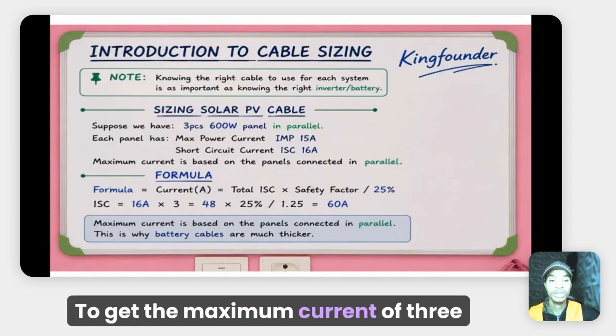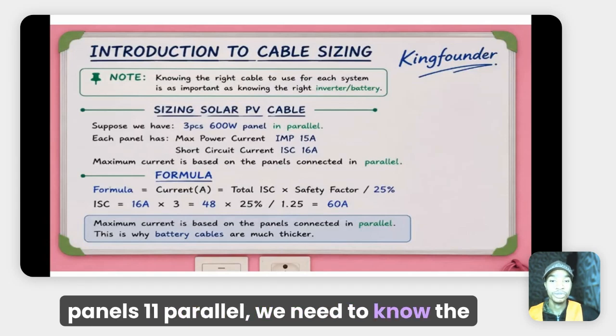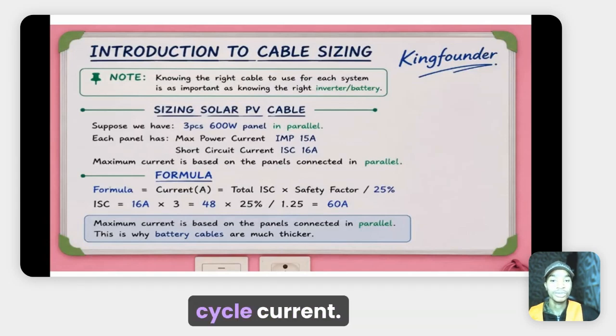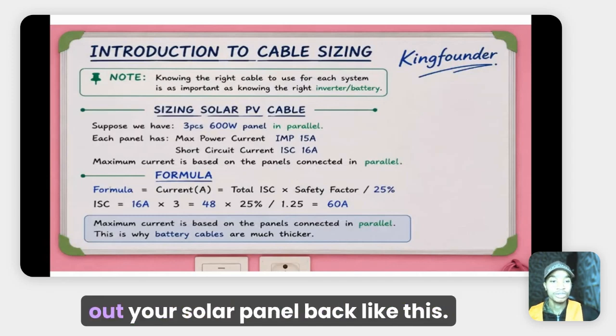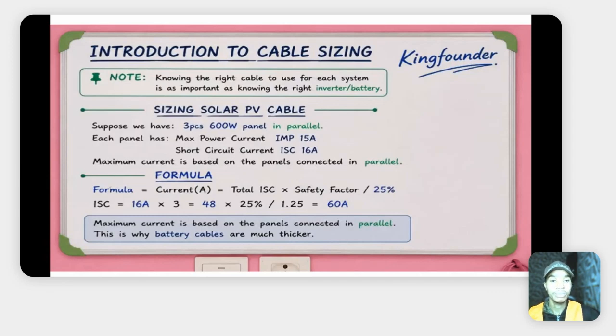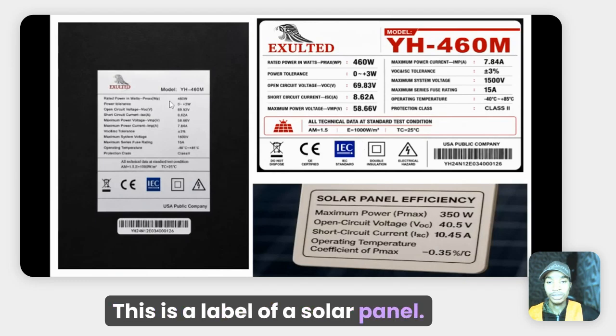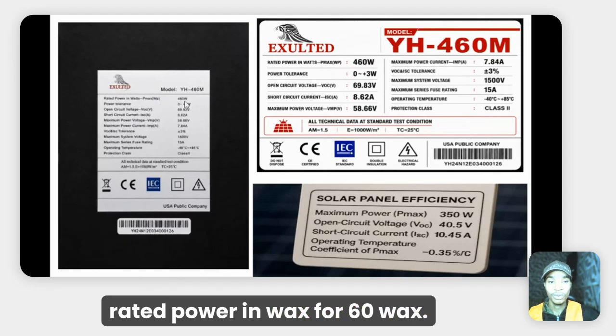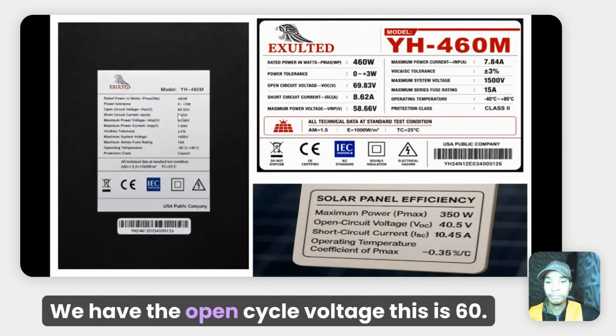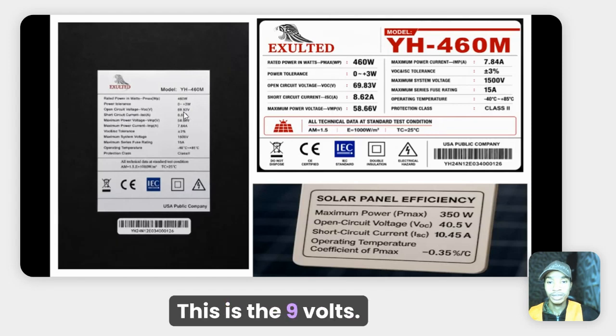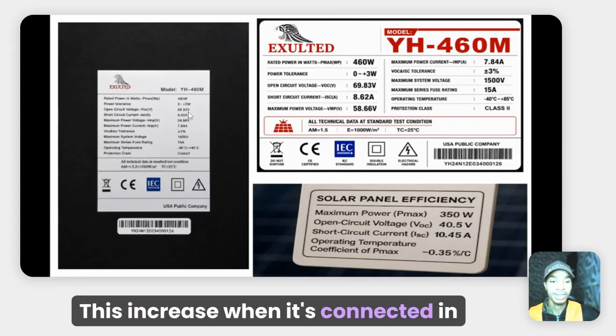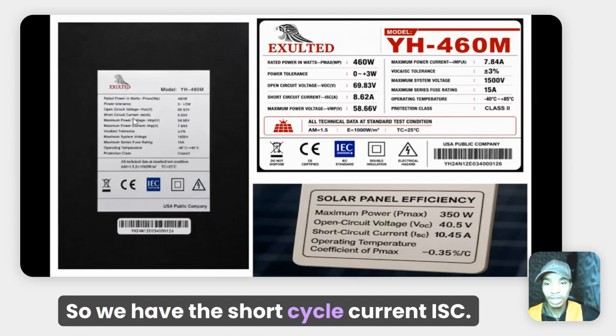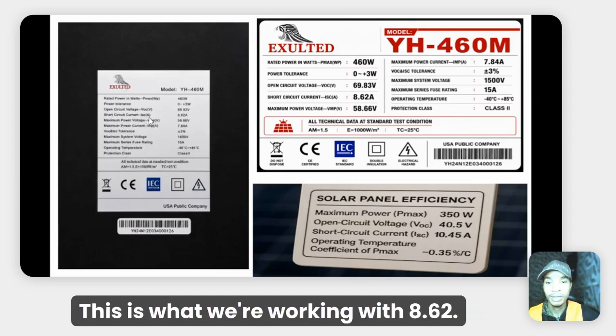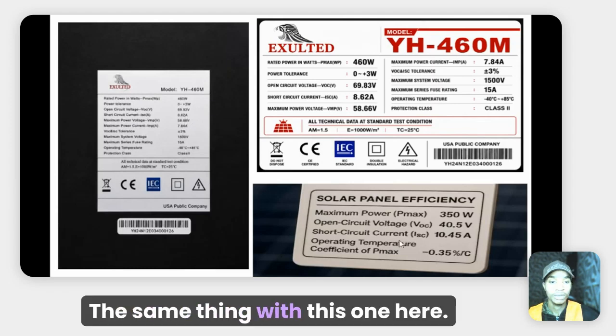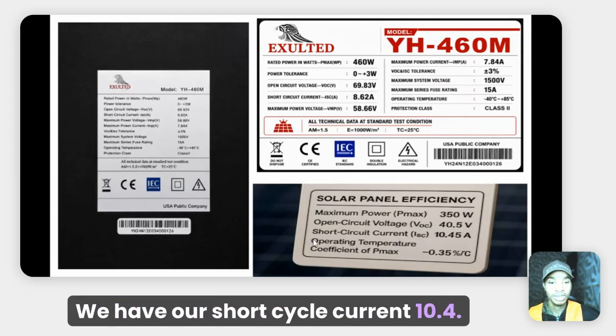To get the maximum current of 3 panels connected in parallel, we need to know the maximum power current or the short circuit current. To simply get this, you need to just look at your solar panel back like this. This is the solar panel, this is the label of the solar panel. So if you look out here, you can see the rated power in watts, 460 watts. We have the open circuit voltage, this is 69 volts. This increases when it's connected in series. So we have the short circuit current ISC. This is what we're working with, 8.62. The same thing with this one here. We have our short circuit current 10.4.